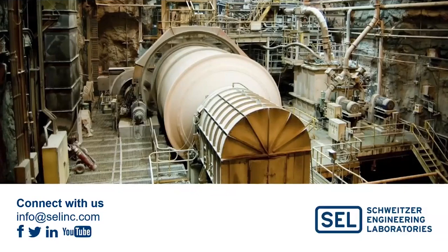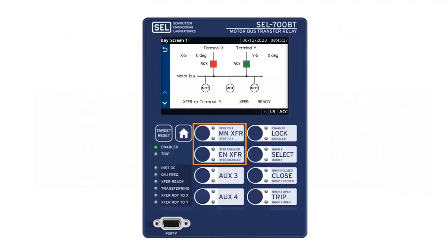And if we go back a couple of slides, you see on the top right it says 0 degrees below the time. And on the other breaker, there is also 0 degrees. That's telling you the angle difference between one side and the other side of the breaker. Obviously, the one on the left is 0 because the breaker is closed. The one on the right is 0 because it just happened to be 0, since the systems are aligned. But if there was a transformer, then that would be 30 degrees, no matter what PT connection you have. So that's telling you what the angle difference is. So basically, you know that you connected right.